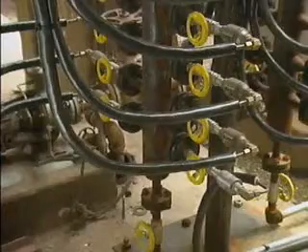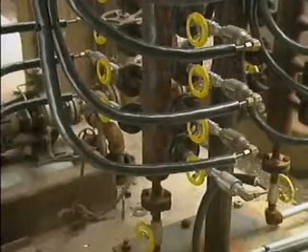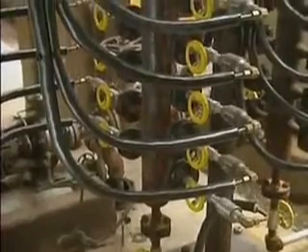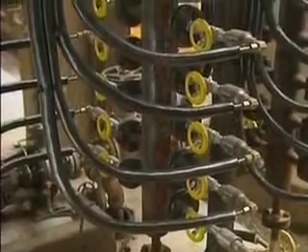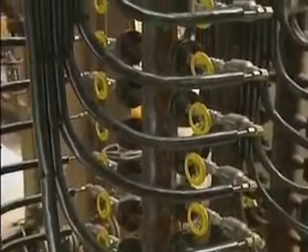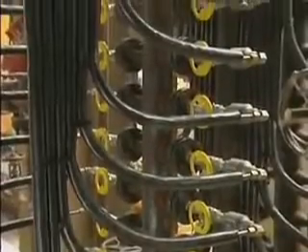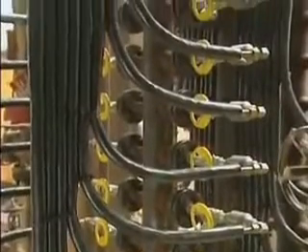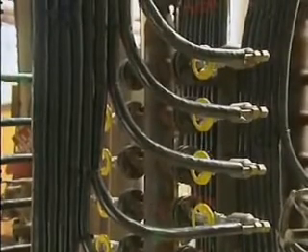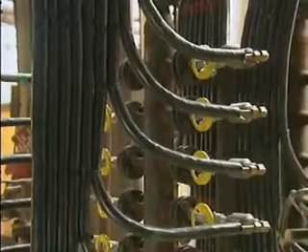Trap surveys based on differences between trap inlet and outlet temperatures can be inaccurate in certain situations. For instance, if a series of traps are installed on a manifold setup so they discharge to a single return line, back pressure may rise because of faulty traps. But the back pressure will rise on all the traps in the system, good and bad alike. So a temperature inspection alone probably won't give reliable information about the condition of a specific trap.